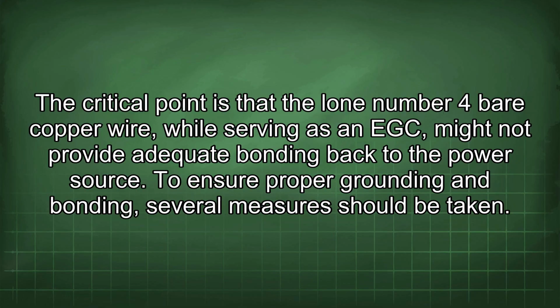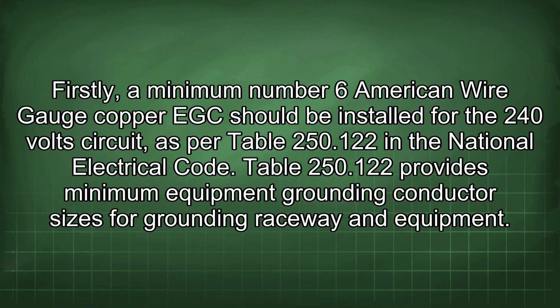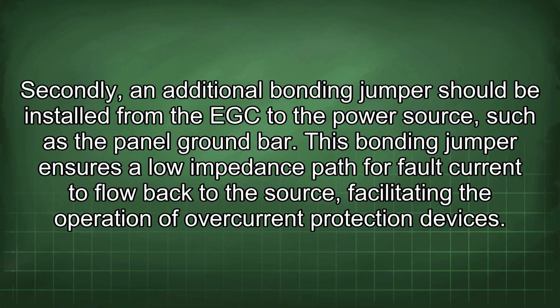To ensure proper grounding and bonding, several measures should be taken. Firstly, a minimum number 6 American wire gauge copper EGC should be installed for the 240-volt circuit, as per Table 250.122 in the National Electrical Code. Table 250.122 provides minimum equipment grounding conductor sizes for grounding raceway and equipment. Secondly, an additional bonding jumper should be installed from the EGC to the power source, such as the panel ground bar. This bonding jumper ensures a low impedance path for fault current to flow back to the source, facilitating the operation of overcurrent protection devices.